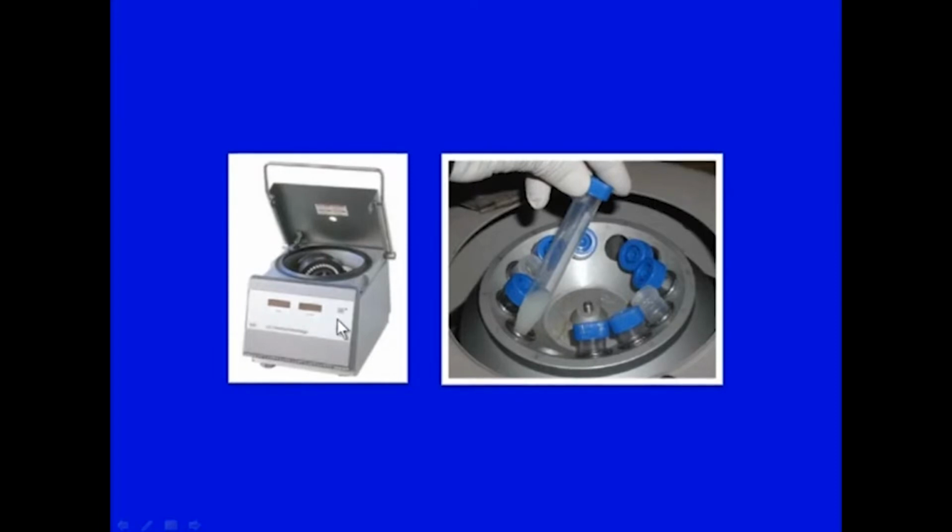means to set the speed limits, and according to the rotor you can set the amount of centrifugal force to be applied. Remember, these rotors specify the kind of centrifugal force which can be applied on them, because the material they are made of can only sustain a certain amount of centrifugal force or stress. So, these are all automated centrifuges, and they function well, and they are also refrigerated for, say, biological molecules which can go bad as heat generation might take place.